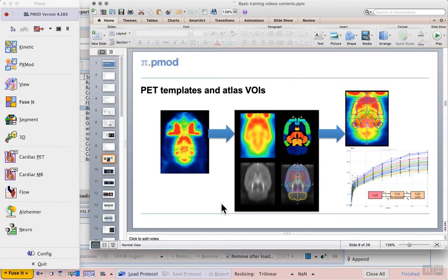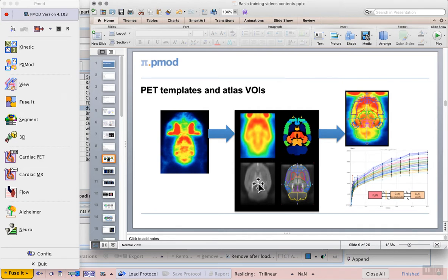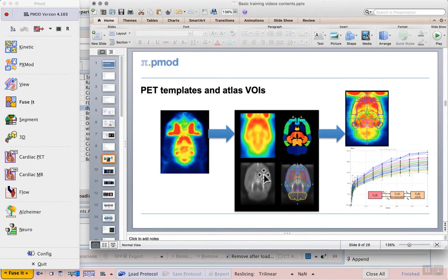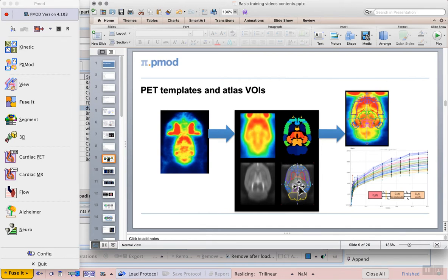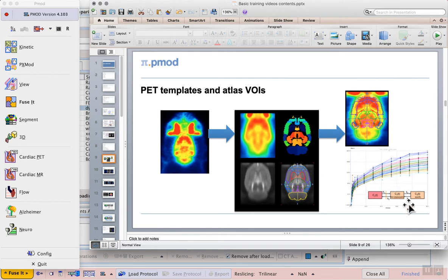Each of our templates corresponds to an ATLAS, which corresponds to an MRI that was used for the anatomical definition of that ATLAS. This means that for a given ATLAS we have a range of templates, whether MR or PET or SPECT or various PET tracers, ultimately resulting in volumes of interest, which can then be directly applied to the individual PET data, allowing us to extract time activity curves for kinetic modeling.